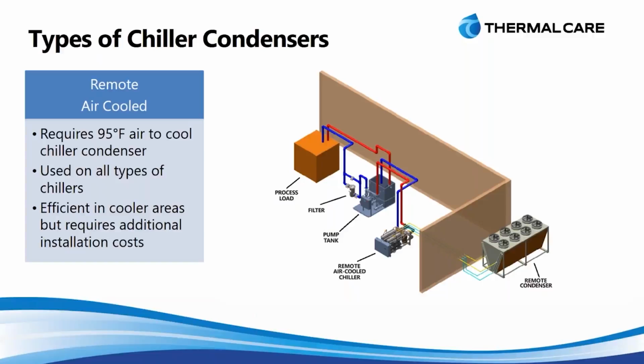The main downside of a remote air-cooled system is that now you have to connect that condenser to the chiller, and that's done with refrigerant piping. So that's copper piping. And that requires additional installation by a certified refrigeration technician. So that installation can be a little more costly. Also, you're a little limited in how far those two pieces can be from one another, and how they can be relative on different planes, one up on the roof, one down below, things like that. So there's more considerations to take in when you're looking at a system like this.